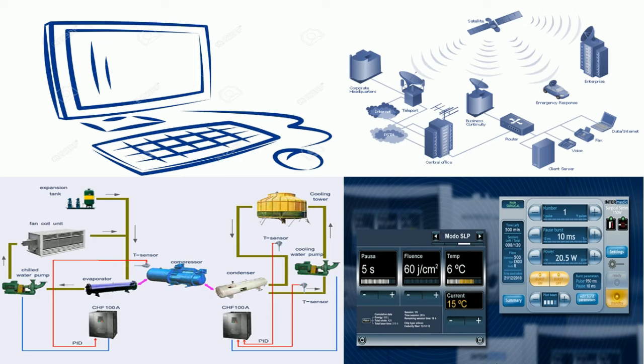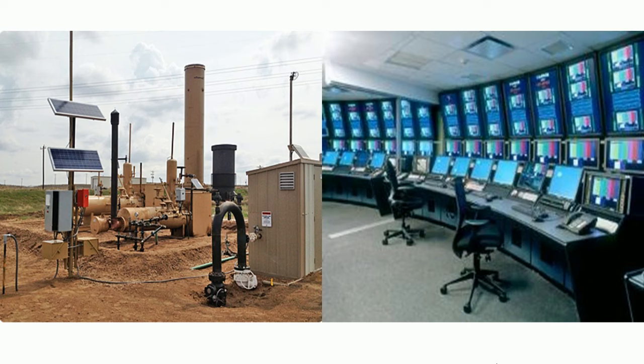SCADA systems have mainly four functions: data acquisition, data presentation, and control. Sensors, either digital or analog, and control relays directly interface with the managed system. The communications network connects the SCADA master unit to the RTUs in the field. Remote telemetry units are small computerized units deployed in the field at specific sites and locations. RTUs serve as local collection points for gathering reports from sensors and delivering commands to control relays.